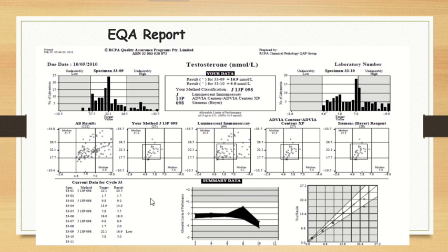The test performance will be accepted based on a specified limit, either allowable standard deviation 2SD or allowable performance limit, which the EQA scheme will decide after comparing to the whole participant group. If your result is outside the specified limit, you need to compare with the same method participants and or with other criteria. If the result is still violated, then you need to do troubleshooting. Afterwards, all the troubleshooting needs to be recorded and presented to the management and staff later on.